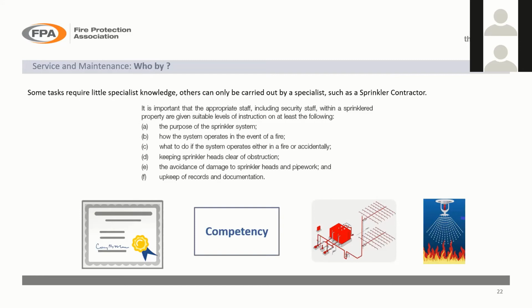So an awareness of the system, the people actually inhabiting the building, looking after it, they need to be clear on what to do and how to avoid damage to sprinkler heads and the pipe work, and also the upkeep of records and documentation. So it comes back to being a question of competency, really, which I know the FPA has spent a lot of time looking into, in other areas as well. But within sprinklers, the people looking after the system should be trained and competent to do that, and that starts with the weekly activities, from the person who just rings the bells every week, right through to your maintenance contractor who comes in and carries out major works and services on your pumps, services on your valves, overhauling and that kind of thing.